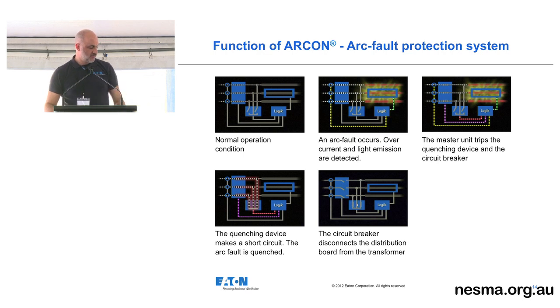The quenching device produces a short circuit. The short circuit is produced purely to take all the energy away from the arc. And that's what the quenching is there. That's how the arc is quenched. While that is going on, another signal is sent to the main breaker, and that trips out the shunt on the main breaker. So it disconnects power to the system. So the system's down, it's safe, everything's ready to go.